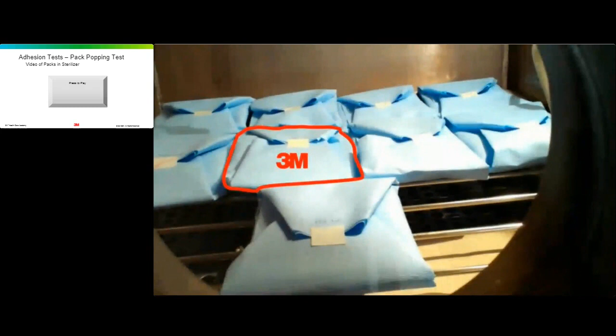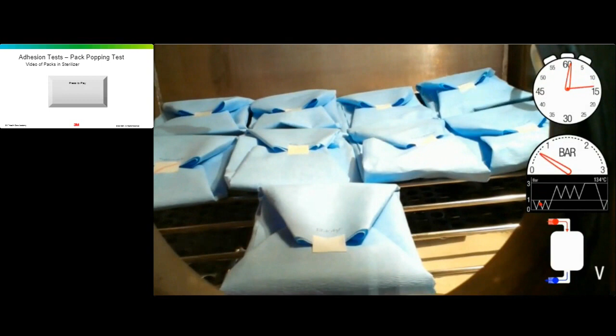You should be able to see this video, and this video was actually taken from inside a sterilizer. There is a window in the sterilizer. And if you look at the right-hand side of this video, you will see some graphics. First of all, there's a little stop clock showing you the time into the cycle. There's a pressure gauge in the middle there showing you the pressure inside the chamber. There's a little diagram below that with a red dot showing you how we're progressing into the cycle, and there's a little graphic at the very bottom showing you the removal of air by vacuum or the entry of steam going into the chamber. So I'll just let you watch this video as it goes along.